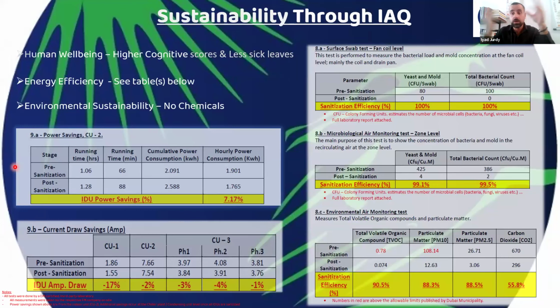The chemicals we're dropping on the coil are ending up in the soil, or they're not going anywhere else—just into our lungs. So for that, we're seeing power savings up to 7% on the fan coil level, the indoor unit level. If you're looking at a chiller plant, you're going to see much bigger savings after you sanitize the whole indoor units. We see it all over the place, some up to 17%, others up to 1 or 2%, depending how dirty the coil really is.